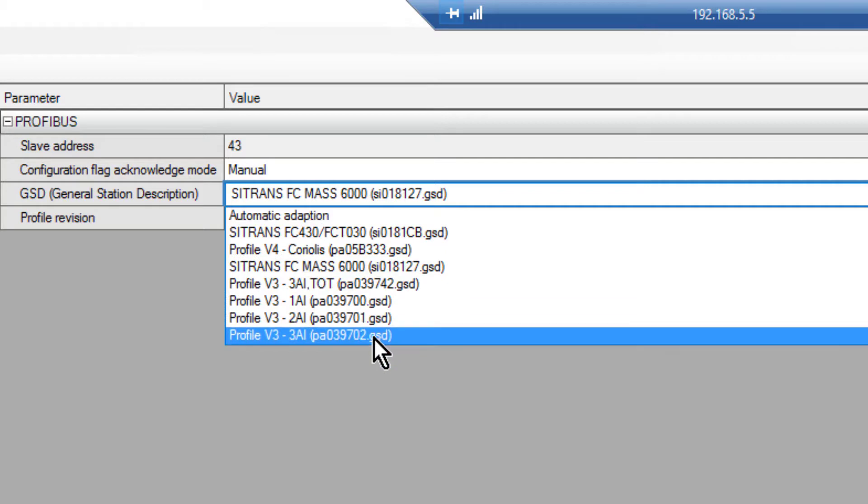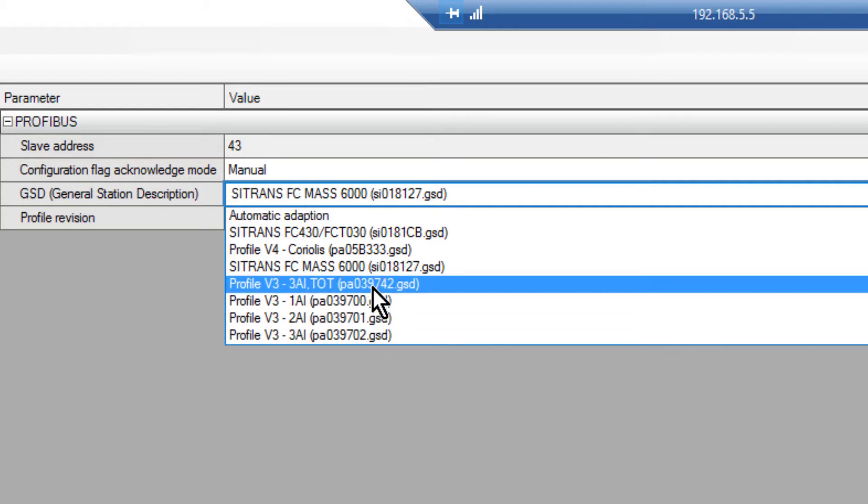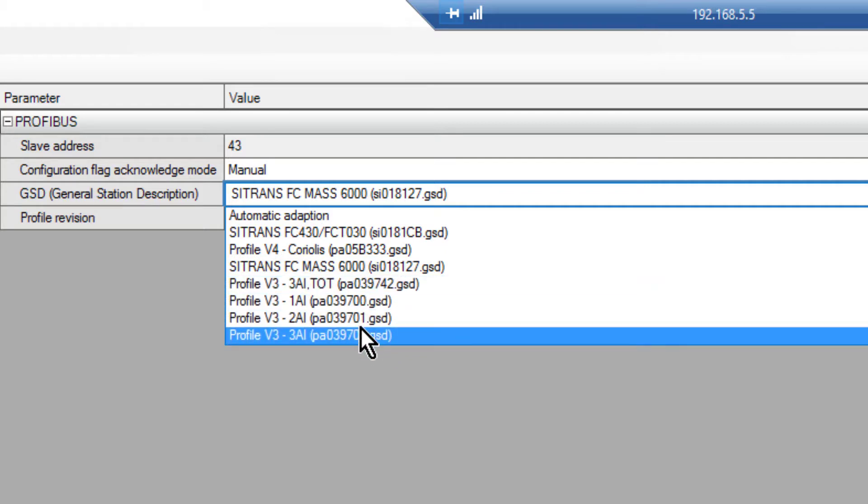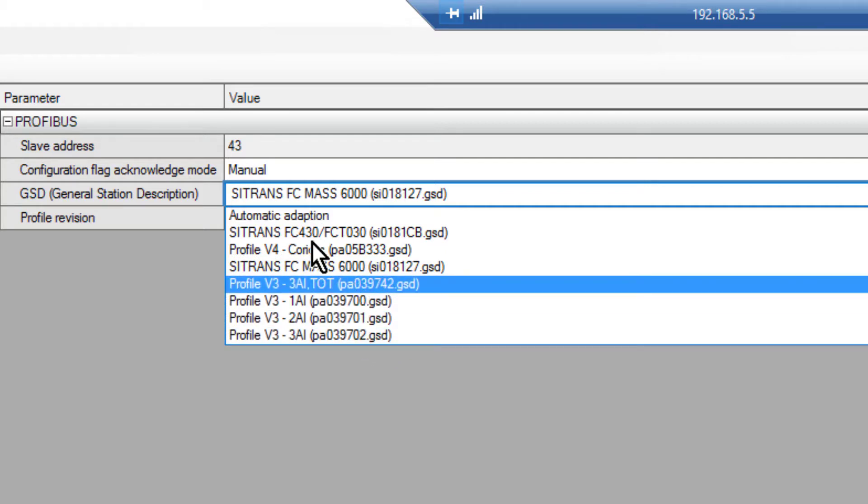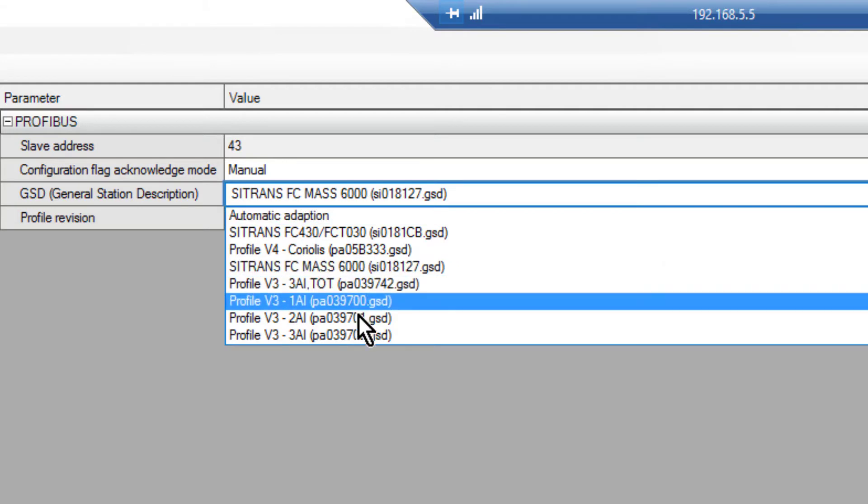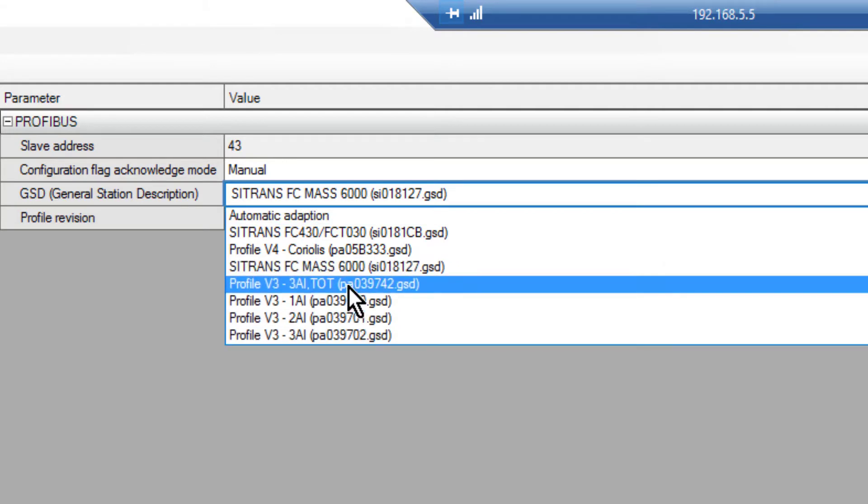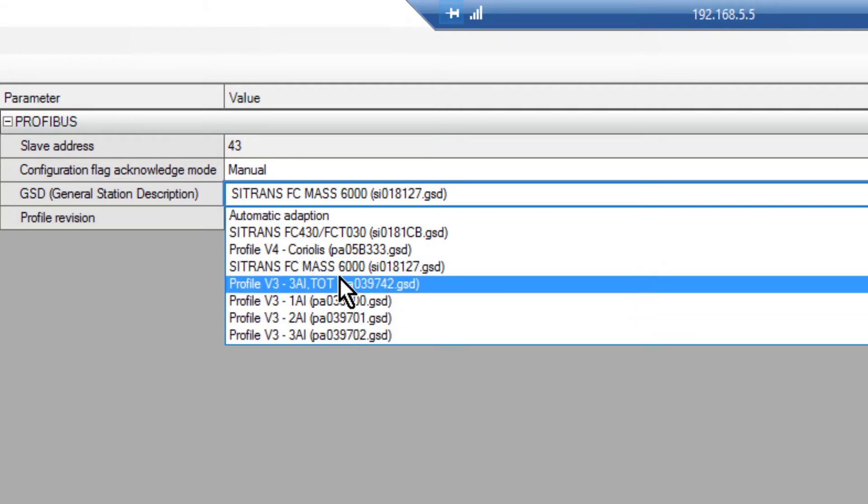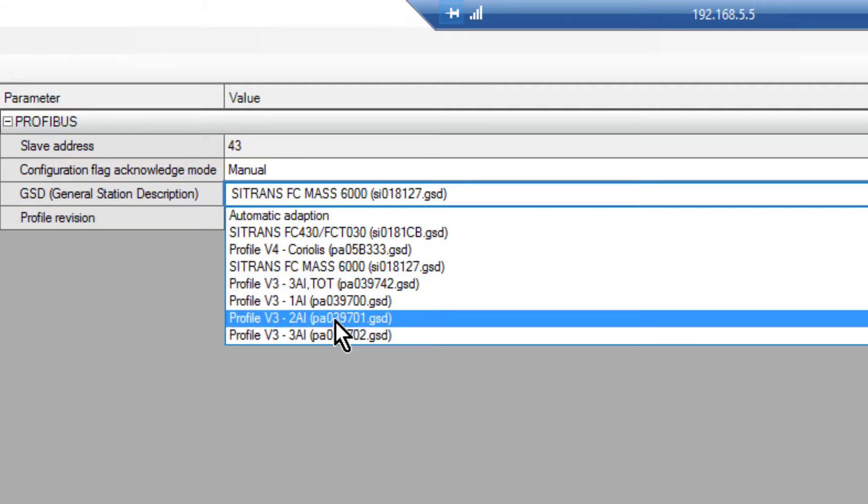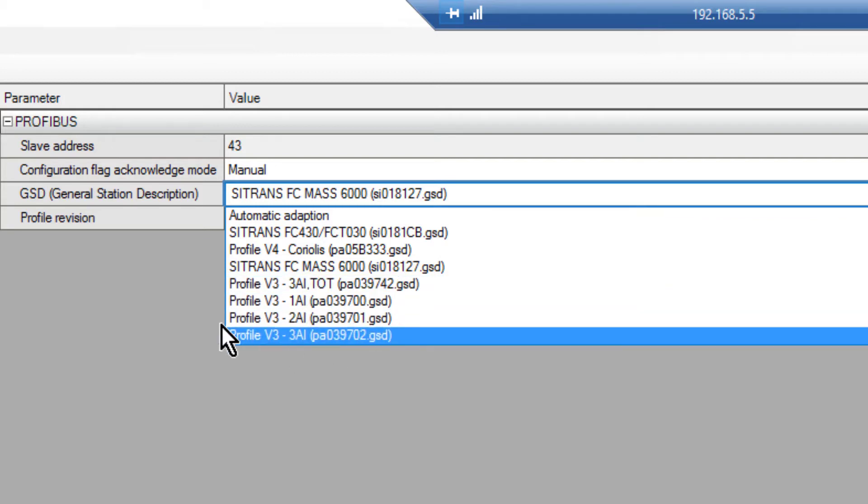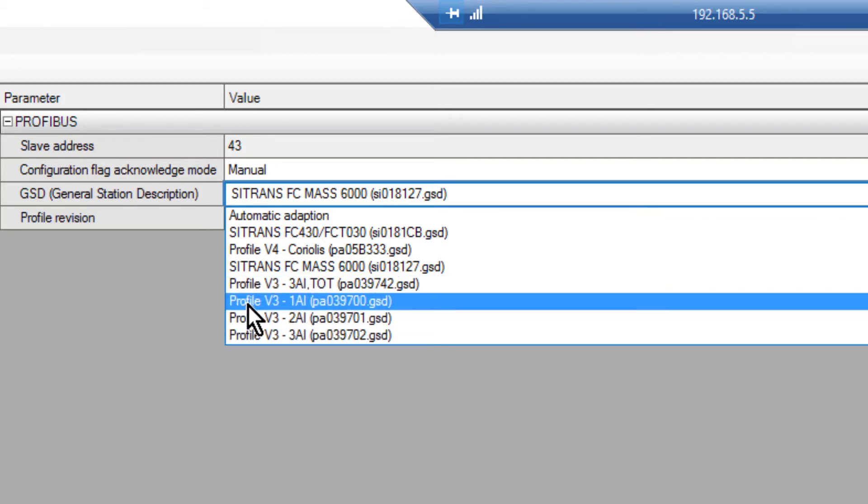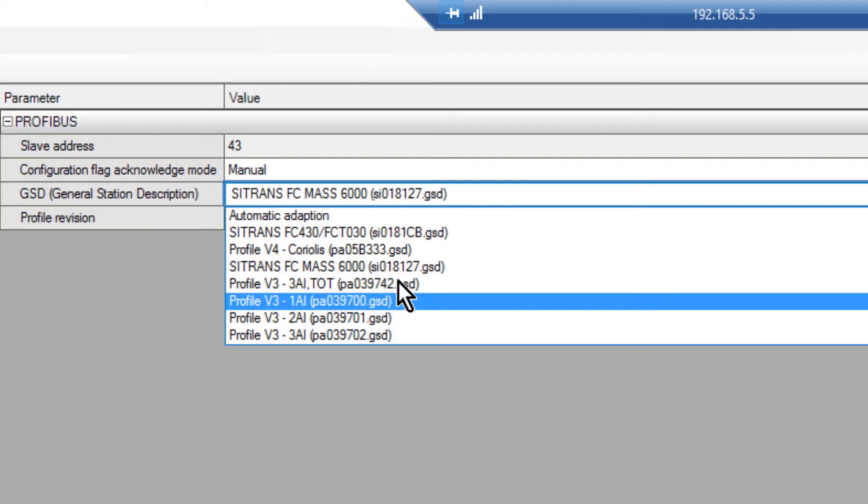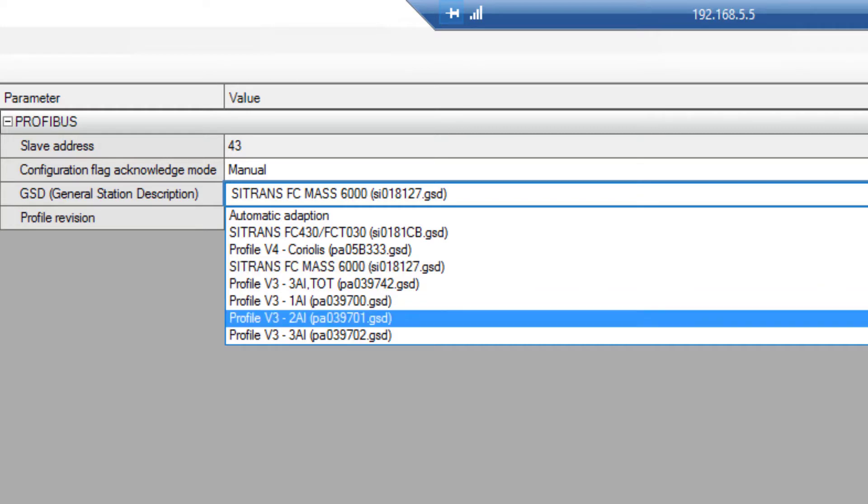Underneath we have the profile specific GSDs and because it's set to automatic, the Compact Field Unit will tell it which one to use within that device. If you had another flow meter that was just giving you the flow value using the generic GSD, when you replaced it with this one you would start transmitting data straight away.